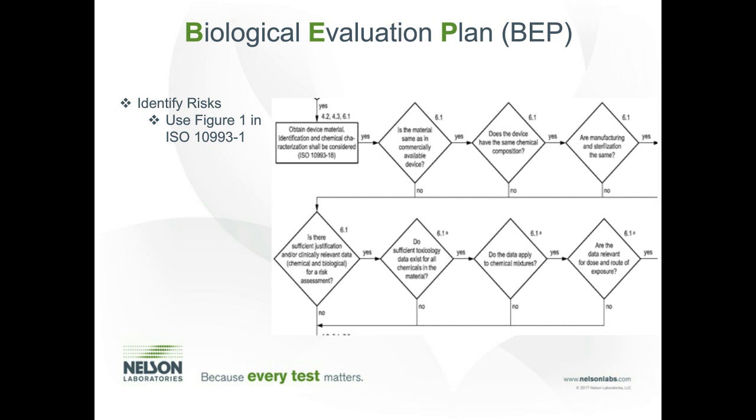Because there are questions in here that you should be asking yourself at the beginning of your BEP, which is, what are these materials? What are the processing? Have I done these materials before with current devices and similar applications? Do I have familiarity with the processing? All these kind of questions you should be able to go through to evaluate the risk of your medical device.